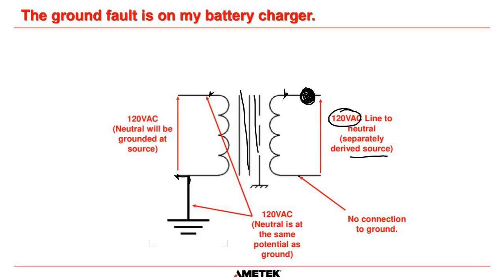What I'm trying to say is, if somebody really, really wanted to, you could actually get a wire and tie this to ground. Not a problem, and that is on the hot side. If that's what you wanted to do, you could do that. But in most cases, on an AC system, you would tie the neutral back to ground and give it a separately derived neutral to ground connection.